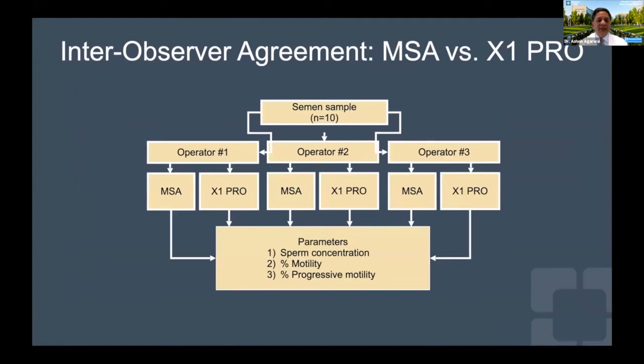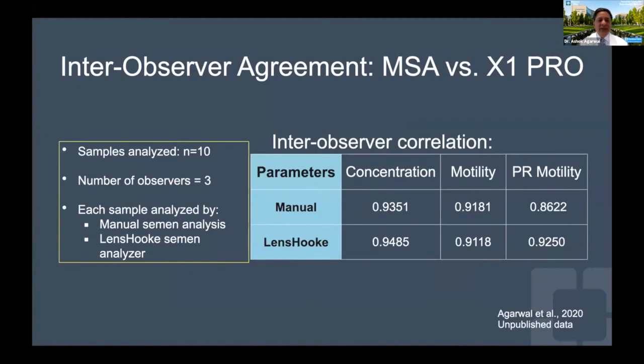Looking at inter-observer agreement — essentially between different operators — three operators counted 10 samples by manual and X1 Pro for all semen parameters. The results show a very high degree of inter-observer agreement of more than 0.9, or 90 percent, for sperm concentration, total motility, and progressive motility using X1 Pro. The results for LensHooke are comparable to manual semen analysis conducted by a trained technologist.